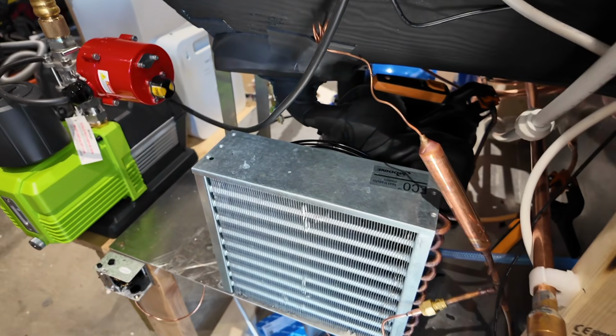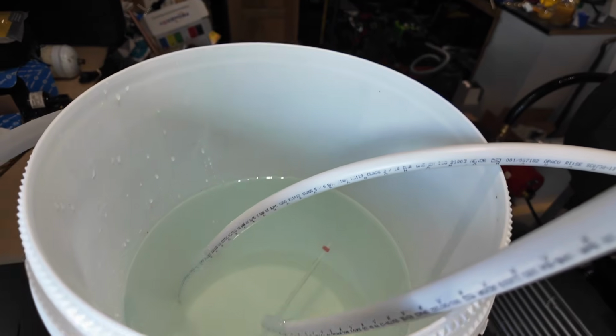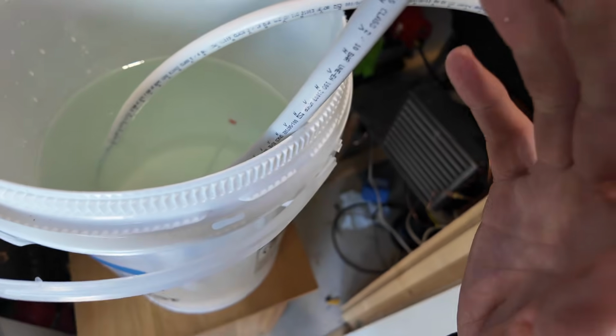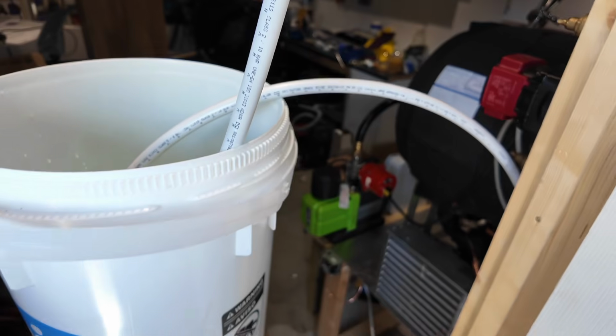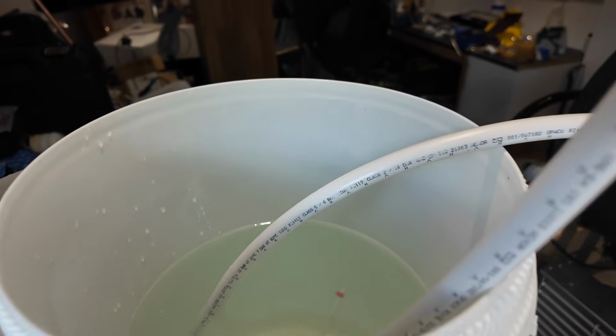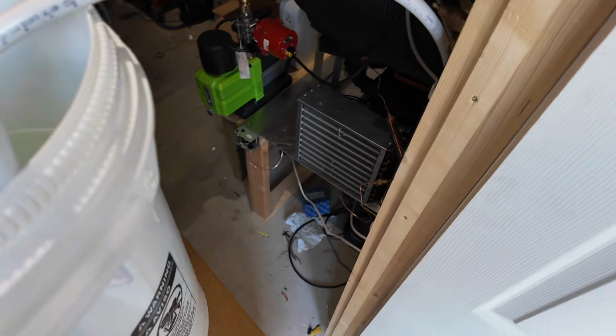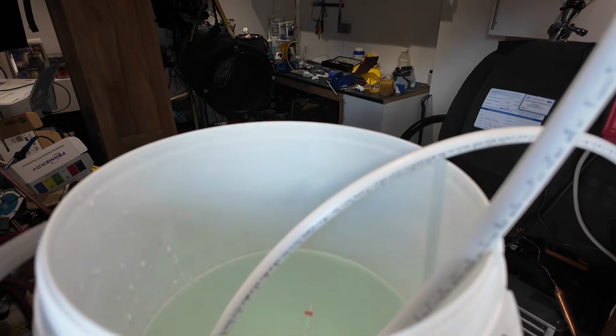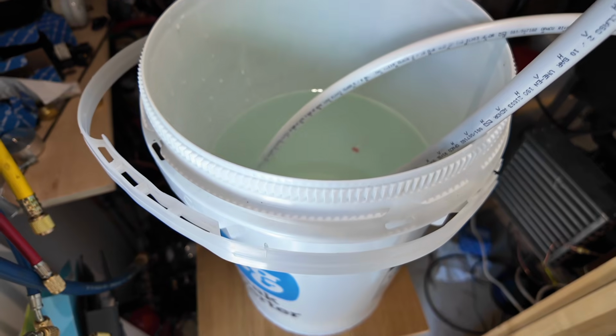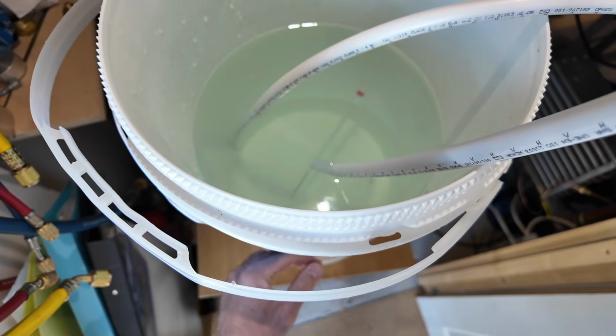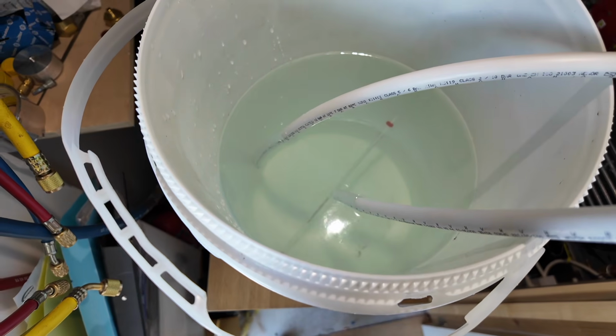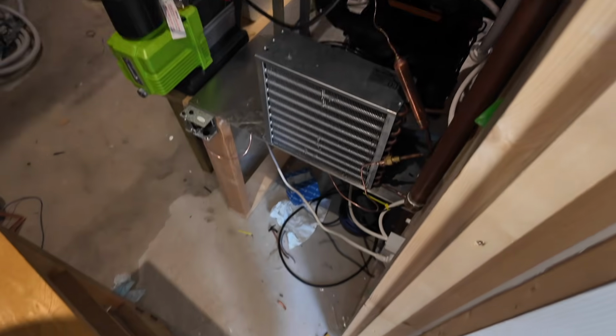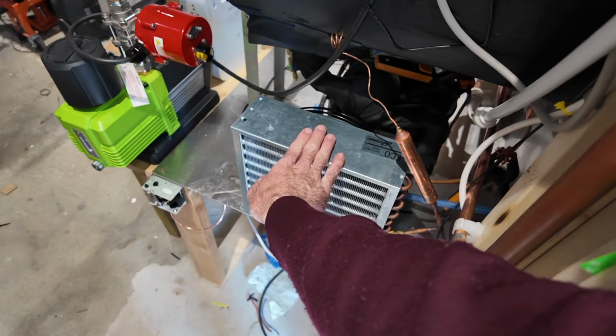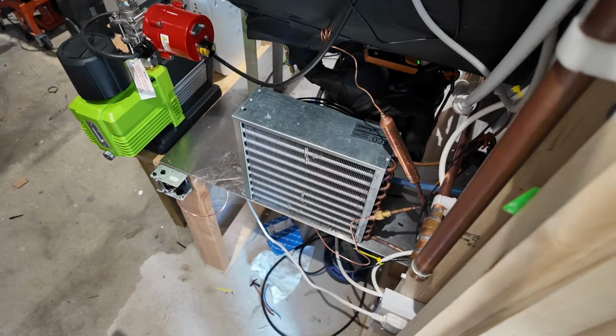This would otherwise just be wasted heat. I think this warrants spending a bit more investment on insulating the pipework and sending it to the main tank in the house, because if this machine runs about 24 hours a day, I think we'll get the tank pretty warm by that time if we can reduce the losses. It also helps the efficiency of the unit, because the condenser is barely having to deal with any heat load.